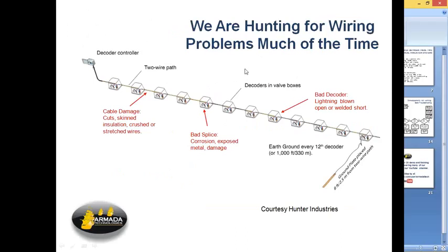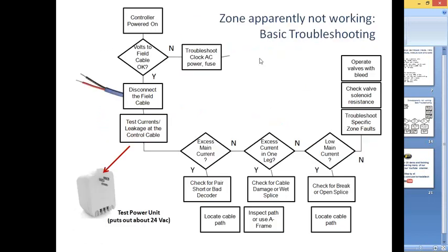So you become kind of an electronic technician for data networks practically when you do this, but we're usually hunting for wire problems. The most common problem in a situation like this is a bad splice, because of the constant power and current flowing through the system and the corrosion mechanisms that go along with copper and other stuff. DBY splices, just to list one manufacturer. So cable damage, cuts, skins, bad splices, bad decoders. You'll find things out there that you're not used to seeing sometimes. Lightning protection, ground protection. Normally you shouldn't have to worry too much about this, but because of the electronics in the system and the length of the chain, they put lightning protection in because they're pretty easily exposed to lightning, especially golf courses and business parks that they have thousands of feet of run of this cable. So that's what you're going to be facing.